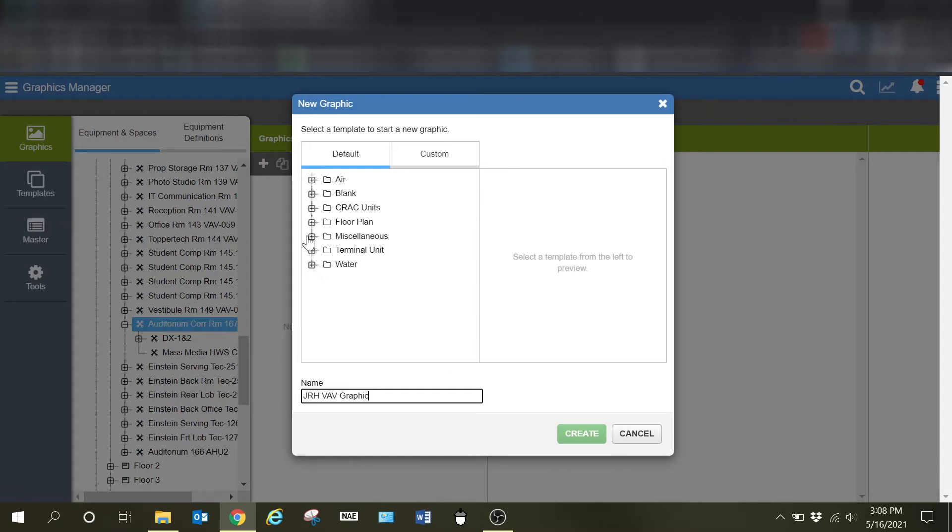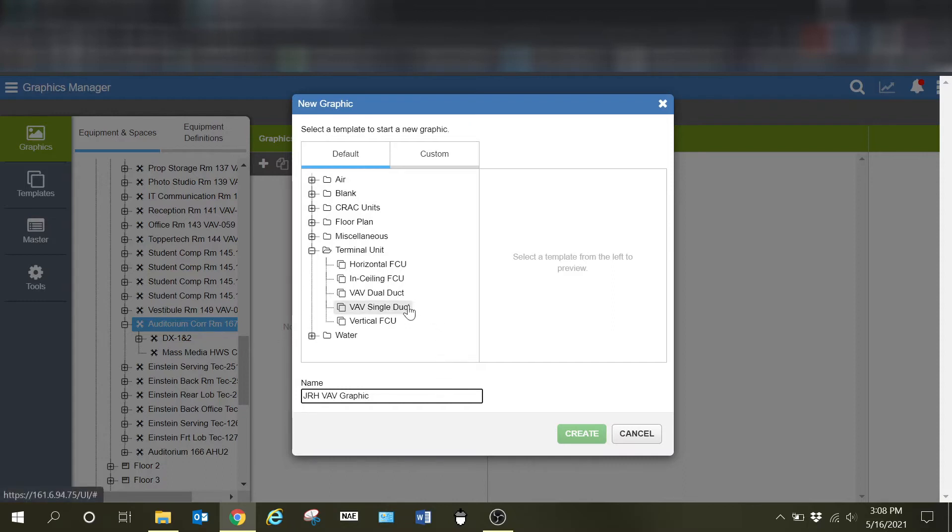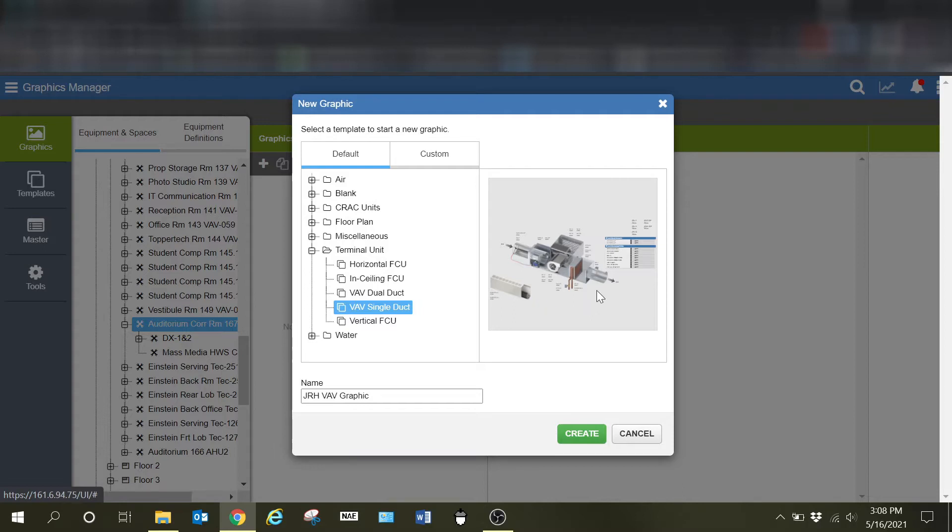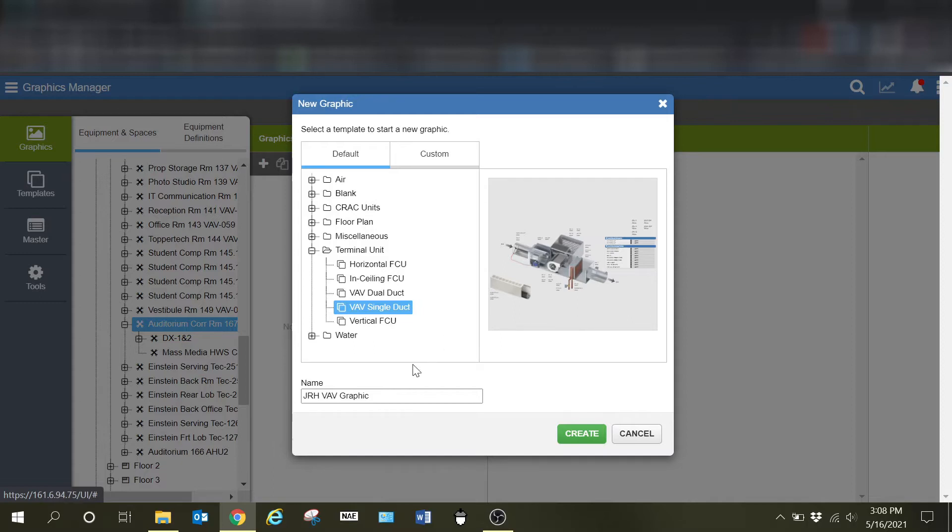Now I'm simply going to drop this down on terminal unit. And what this particular device is, is a single duct VAV. So I will select that. It's going to give me a little display of what it's going to be coming up with. And you're going to see with this particular device, there's a lot of information here that is not going to be part of this particular VAV. However, these points are all aliased, which means it's only going to pull relative points to this particular device. So I'm going to hit create.